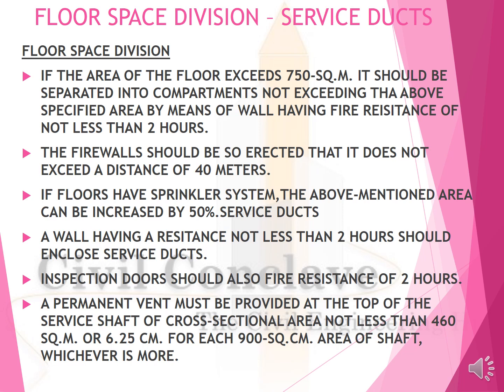Floor space division, that is, service ducts. If the area of the floor exceeds 750 square meters, it should be separated into compartments not exceeding the above specified area by means of walls having fire resistance not less than 2 hours. The fire wall should be so erected that it does not exceed a distance of 40 meters. If floors have a sprinkler system, the above mentioned area can be increased by 50%.